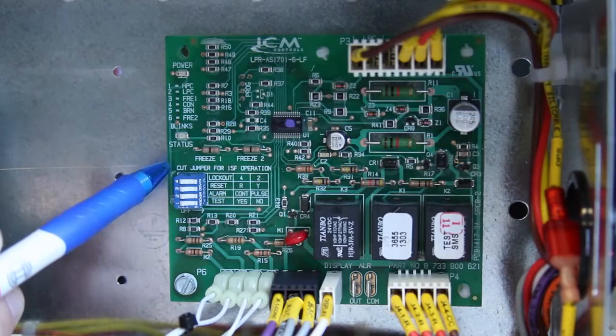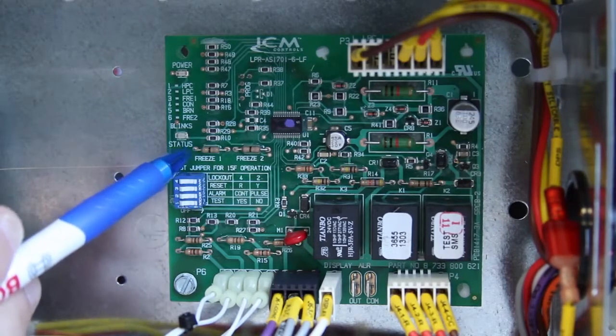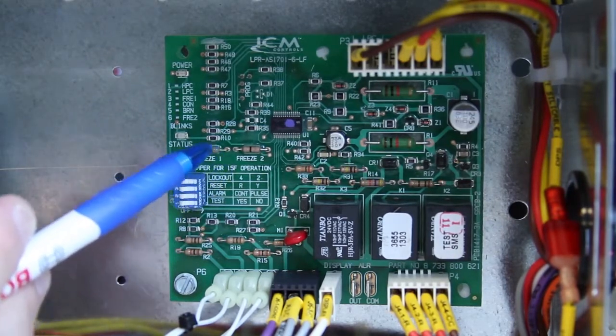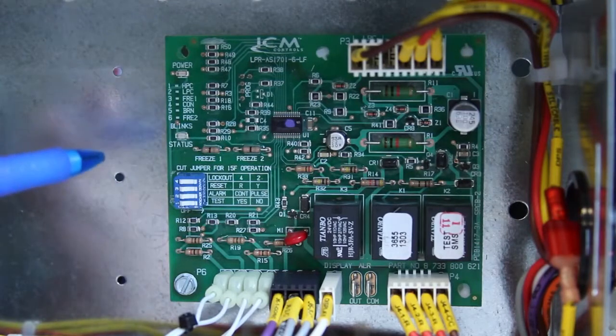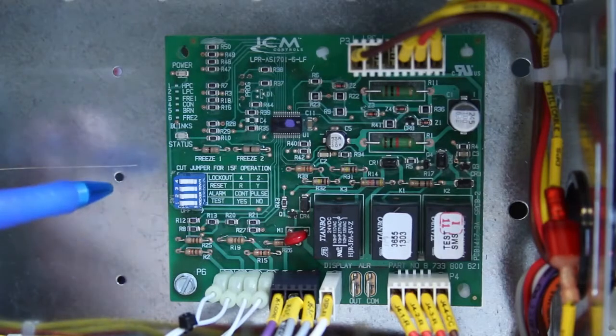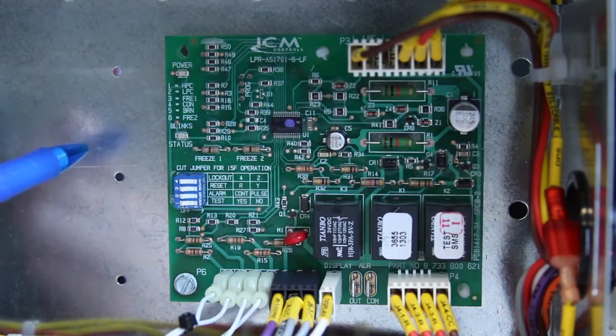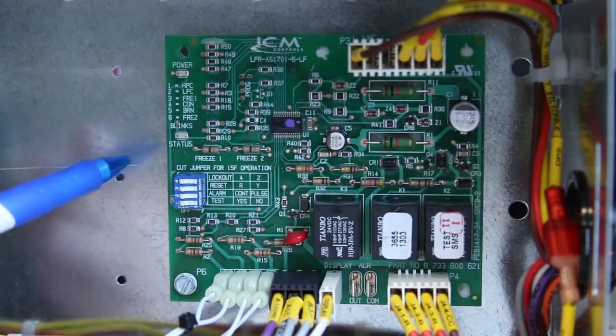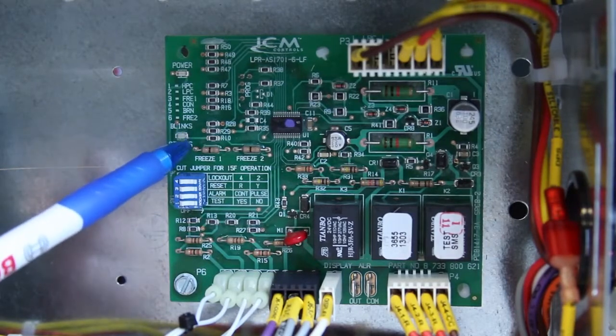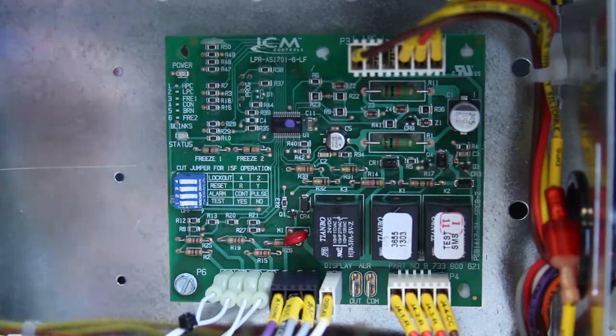Just above that set of dip switches are 2 jumpers, one marked Freeze 1 and one marked Freeze 2. The sensors come default at 30 degrees, so if the water or air temperature reaches near freezing, the unit will go into a soft lockout when those sensors reach 30 degrees. On the water coil, if you're operating it on a closed loop system with glycol and you want to operate it below 30 degrees, you have to cut the jumper that is labeled Freeze 1, and it will reduce the cutout temperature to 15 degrees.